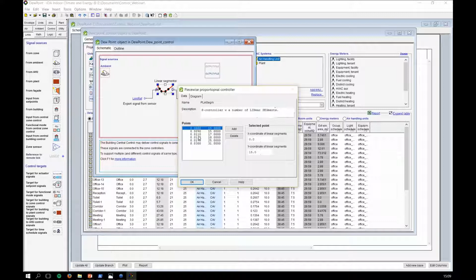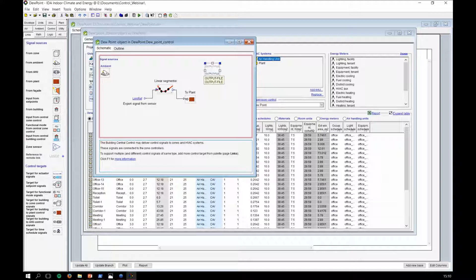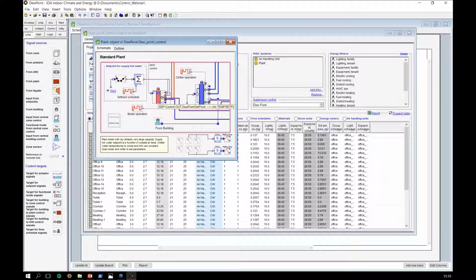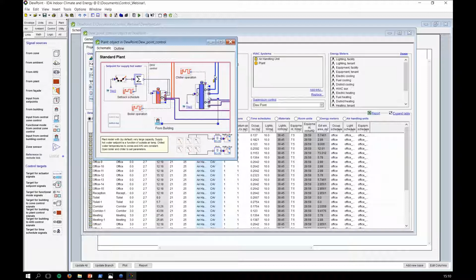Then I'm exporting this signal to my plant. This export to plant, you can find in links under targets. My target here is from building to plant control, and as always, I have an output file to log. If I open my plant, I see this import from building to plant control output. If I double click it, I see the dew point set point is what I want to get from this. I'm feeding it to my chiller, to the set point that dictates the temperature of the cold water going to the zones. This channel here is going to the air handling unit, and these pipes here are going to the zones.